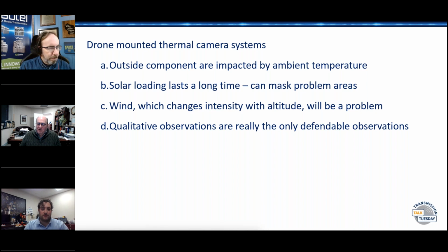If you need to go up a tower and look at stuff like an antenna or transmission line, you can get up close with a drone and take thermal readings. But you don't want to do this in the middle of the day when the sun's shining on it, because you're fighting against the sun, which is many degrees Kelvin compared to the system. So you want to wait until after dark, which means you have to be certified to fly at night, and you have to wait long enough after dark for the thermal loading to cool down, like a pot on the stove - you turn off the stove, but you have to wait for it to cool down, for ambient temperature to take over. So now you're looking at the transmission lines running, not the sun's impact.